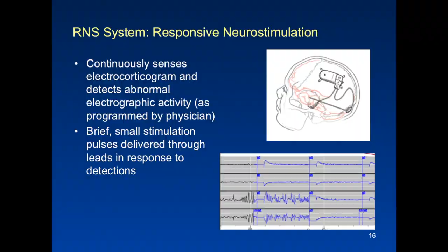But here's an illustration. This is a recording from a patient. And here there are 4 channels that are recording, in this case bipolar. What we are seeing here is that a discharge is developing, which I think anybody would call epileptiform at this point. The device has been programmed to detect fast frequency, high amplitude activity. Here is the detection. And here is the stimulation. The device then redetects, and if it detects something ongoing, will deliver another stimulation. In this case, it has looked at it and said there's no redetection. And this can go on up to 5 sequential stimulations, and each stimulation has 2 bursts, and every burst can deliver a different kind of stimulation. So here, again, I'm saying we've got a lot of variables, which is good, but it's also a little bit of a problem in terms of how we analyze all this data.